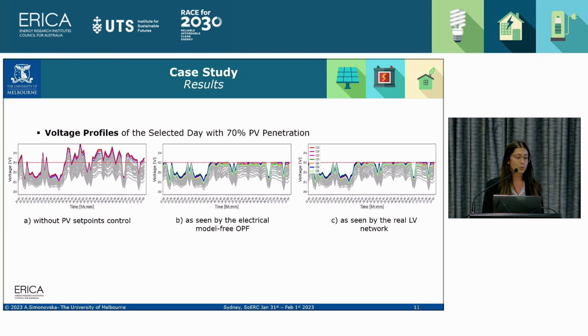Lastly, the voltage profiles of the selected day with 70% of PV penetration for the low voltage feeder. On the left side, you can see the voltage profiles without having the PV set points, whereas in the middle are the voltage profiles after running the electrical model-free optimal power flow. On the top right, we are using the produced settings to run a power flow now, just to see whether these settings are correct or whether we will have voltage problems after using them.